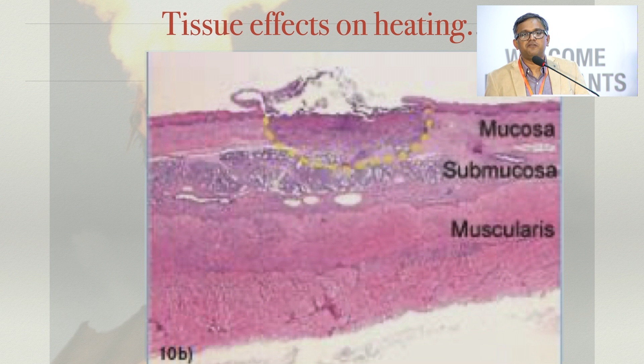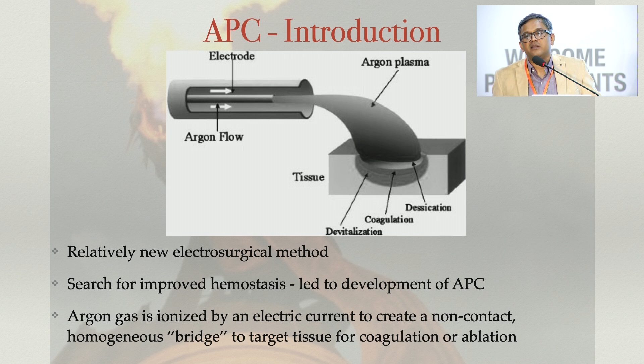So let me introduce argon plasma coagulation, which is actually what I am concentrating on, and I told you Nirmal is going to talk about electrocautery. So what is basically APC? It's a new electrosurgical method, and the bleeding is the one which actually got the gastroenterology and the surgical community to come together to decide and discover this modality, and that's how the development of APC came along. So it's bleeding that is the central focus of argon plasma coagulation. And basically what happens in this is argon gas is ionized by an electric current to create a non-contact homogeneous bridge. And that's basically the bridge that with the transfer of heat causes coagulation and ablation.